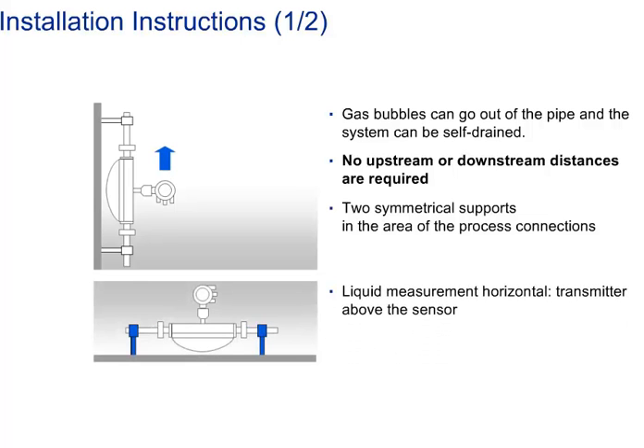For liquid measurement in horizontal orientation, the transmitter should be above the sensor to avoid any gas bubbles remaining in the sensor.